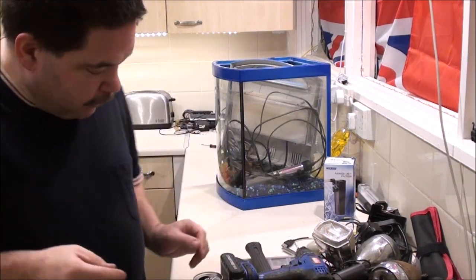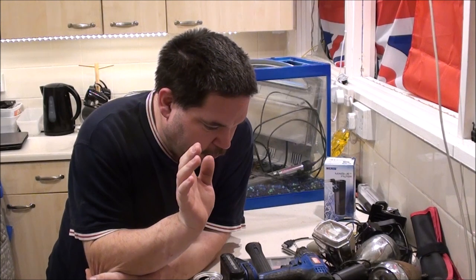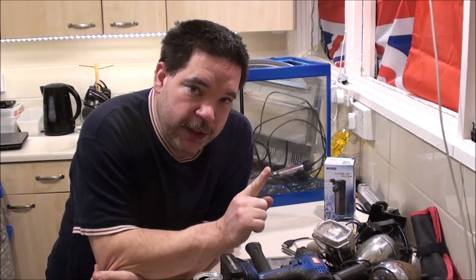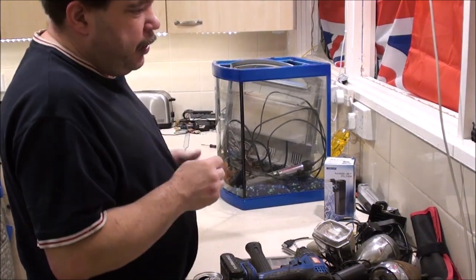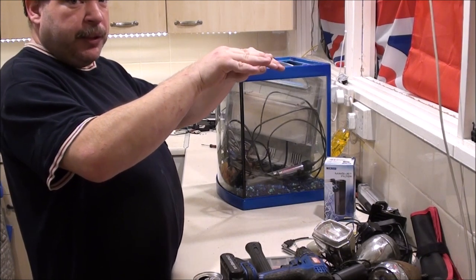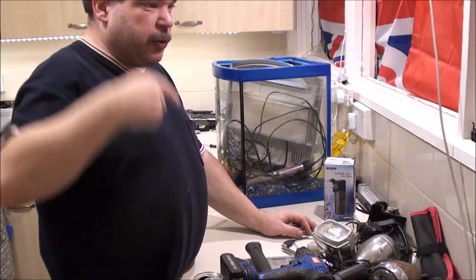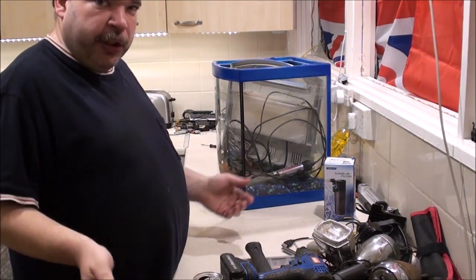So they want to do that, but he realised there are two things that make it awkward. One — mine's at the top. There are six flats in total, seven if you count the communal electrics. The cupboard door partially covers mine, which means there's really not a lot of hand room for screwdrivers. Also, he's got to pull the incoming mains fuse, which you actually need permission from the electrical company — UK Power Networks — to do. Even electricians can't just pull the mains fuse, and everything up here would have to be off to prevent arcing when he puts it back in.